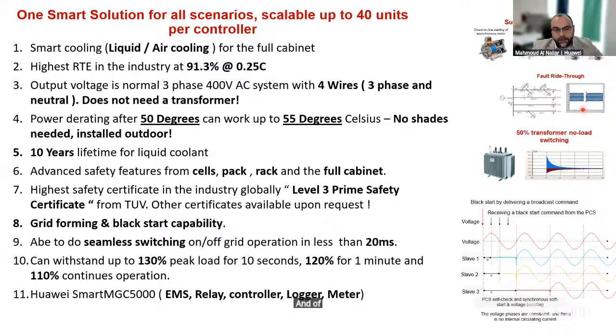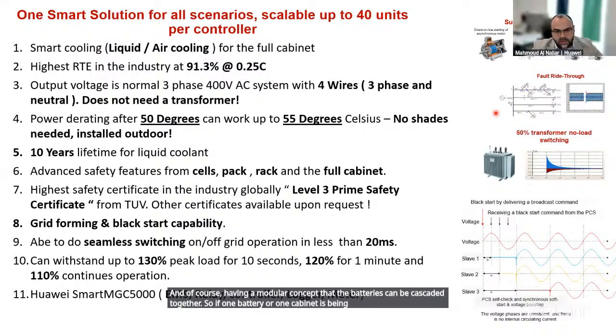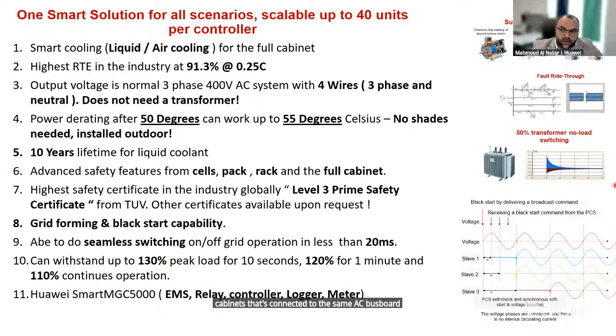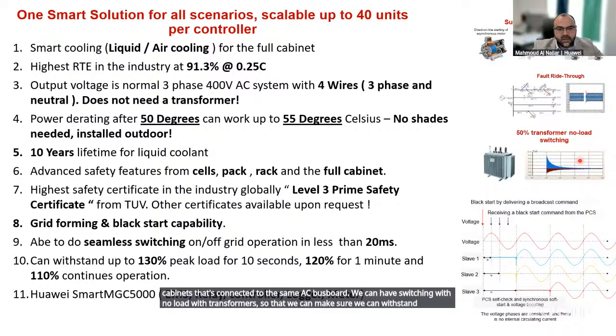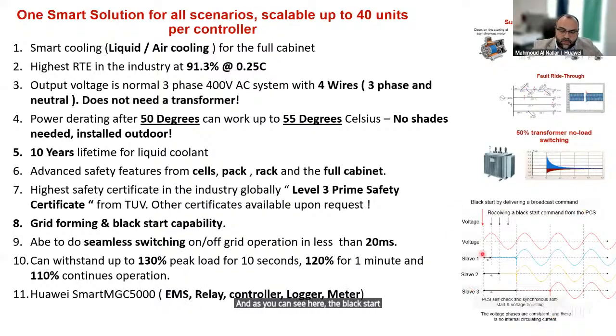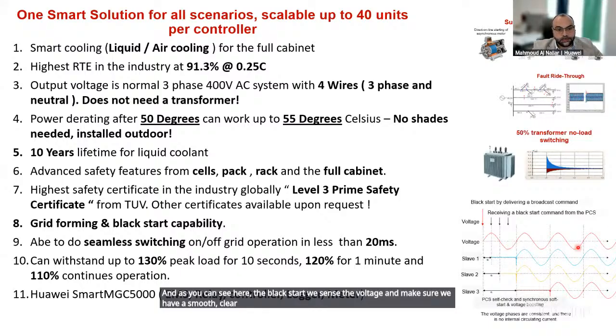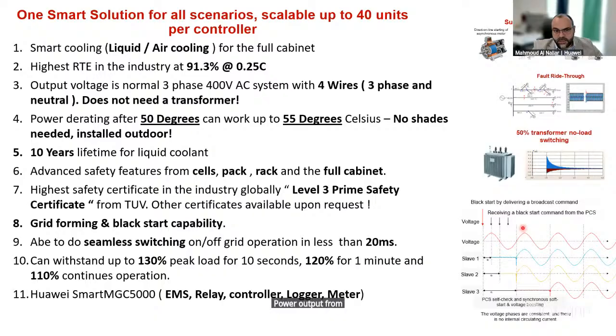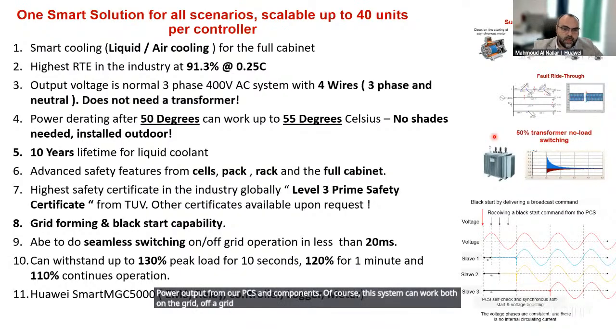And of course, having a modular concept, the batteries can be cascaded together. If one battery or one cabinet is affected, we make sure it's not affecting the other cabinets connected to the same AC busbar. We can have switching with no load with transformers, so that we can withstand the inrush current that we are getting from the transformer. And as you can see here, in the black start, we sense the voltage and make sure we have a smooth, clear sine wave power output from our PCS and components. Of course, this system can work both on the grid and off the grid, in multiple operation modes, as we discussed earlier.